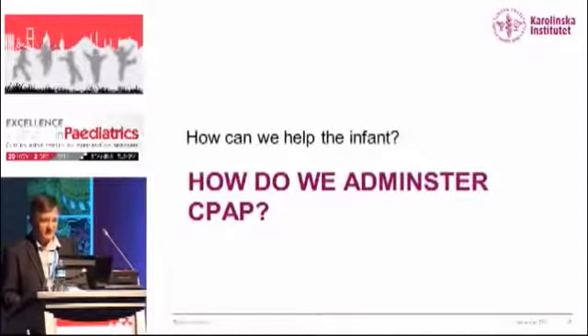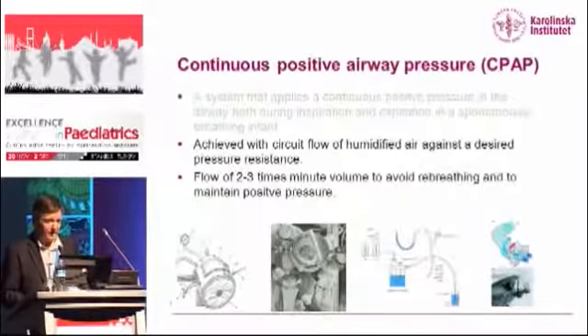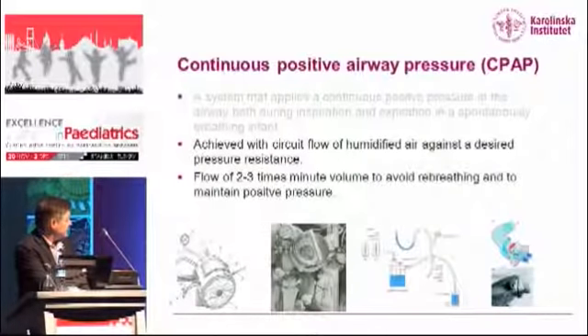So how do we administer CPAP then? That's a very interesting question, I think, because traditionally it's a circuit with humidified, heated air against a pressure resistance, which basically inflates the lung. And it's classic to say that the flow needs to be about 2 to 3 times the minute volume to avoid rebreathing. And this is the basic, old water seal CPAP system, which is very simple. Basically all you need is water tubing and a gas flow.